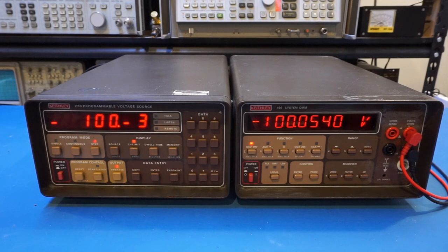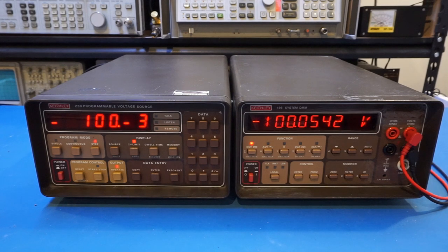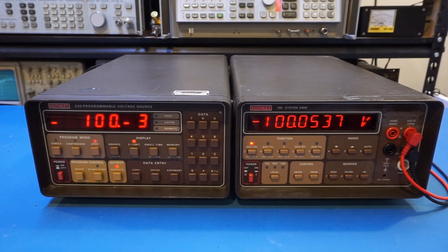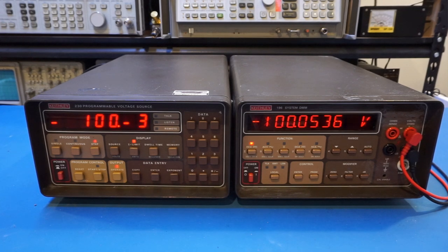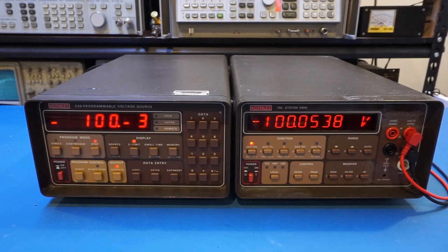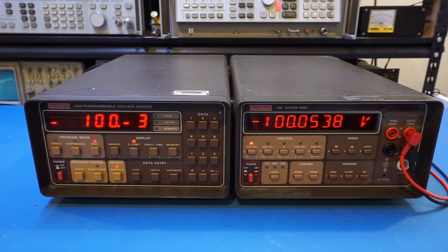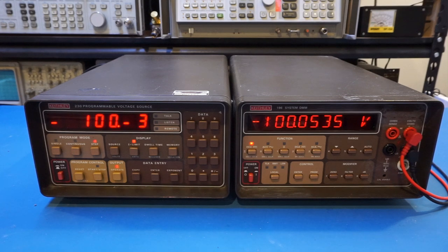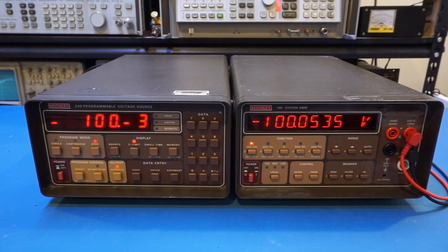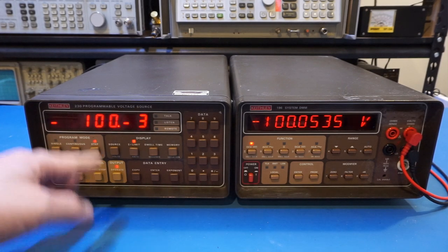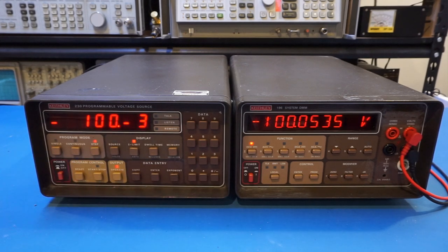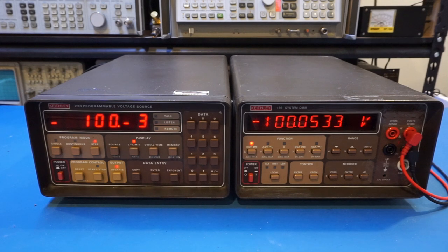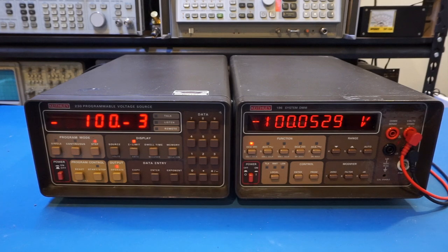So of course, being a programmable voltage source, we could do a lot more things than we just did using the front panel here. One potential use of this programmable voltage source is to do some automated testing via GPIB. So all the commands that we did from the front panel can also be done using the computer via the IEEE 488 interface. Another useful function of this voltage source is that we can store multiple data points, in this case up to 100, and then later on, playback using either a single shot or continuous playback. And based on the dwell time and voltage settings, you can potentially generate some interesting waveforms to test your device under test. So that's something we're going to take a look at next.